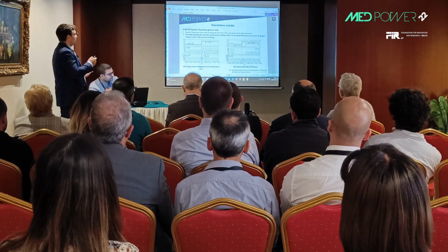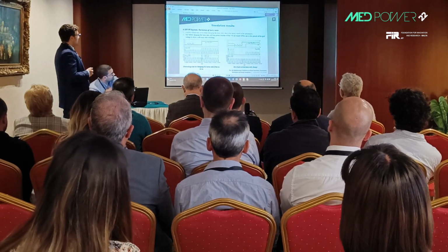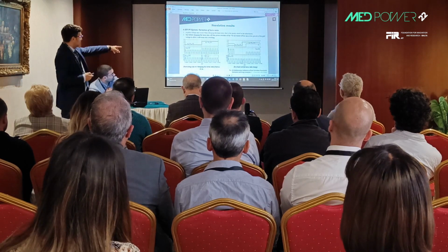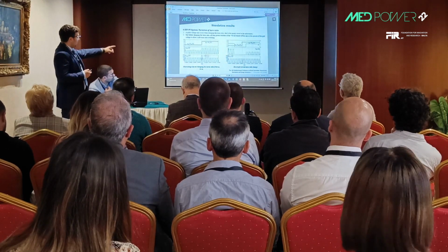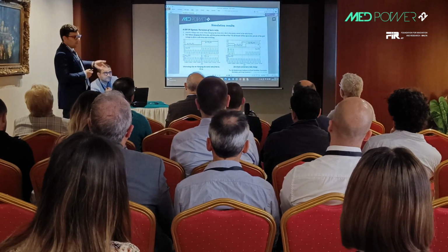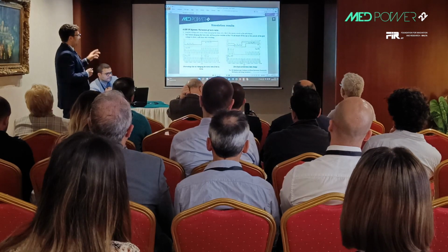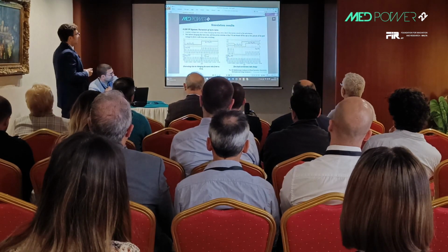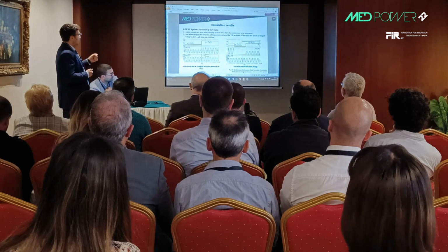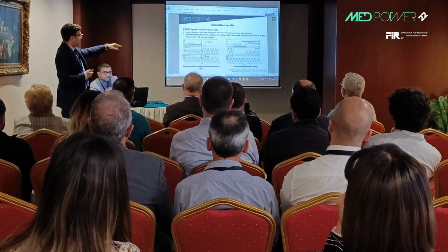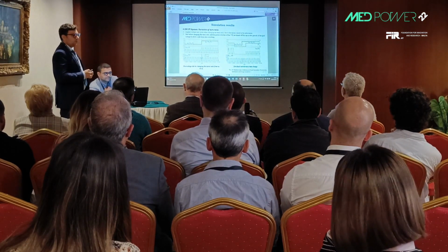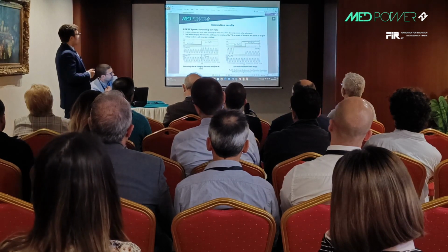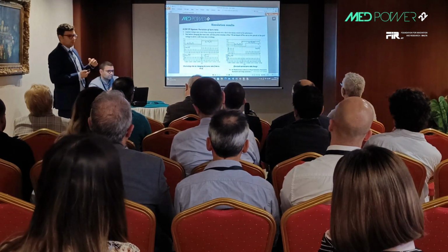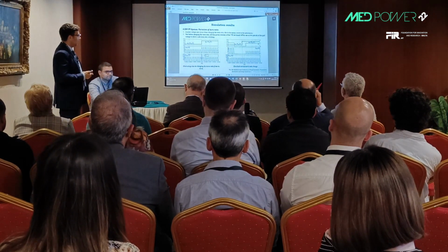When we change the turns ratio, we have a problem, because in the secondary voltage of the transformer there is an overvoltage, due to energy stored in the inductance. For this reason, just before changing the turns ratio, we turn off all the power switches of the full bridge in order to have zero load current.